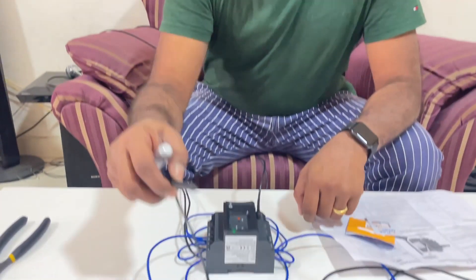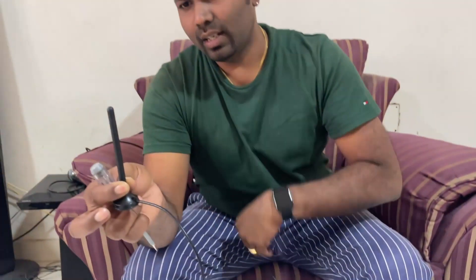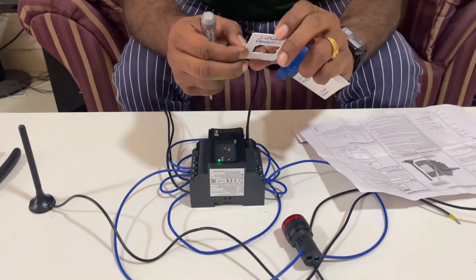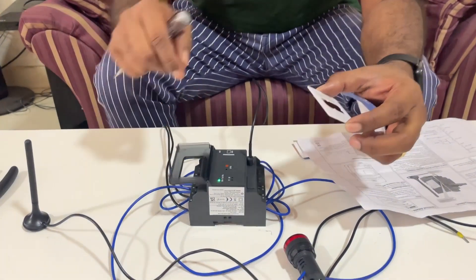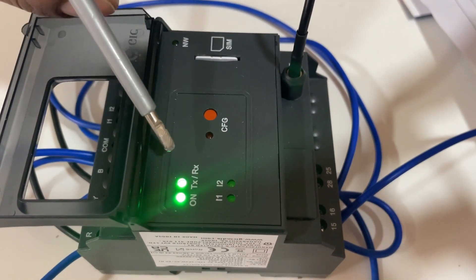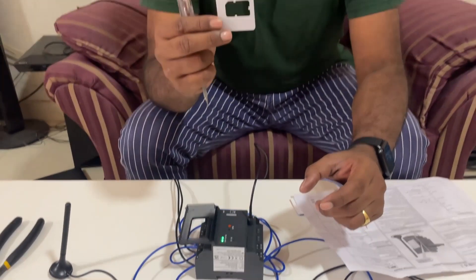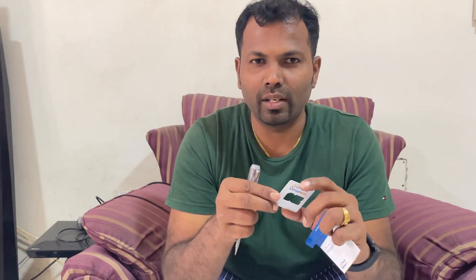There is also an antenna — this aerial connects to the GSM modem and receives and sends signals to the master numbers. We also need a full-size SIM card, as only full-size SIM cards fit into this GSM modem's SIM slot. There are indication LEDs for input status and GSM modem status. Use a postpaid SIM card and make sure the SIM card signal range is available in your equipment or pump station area — only then can you control and operate by phone calls.